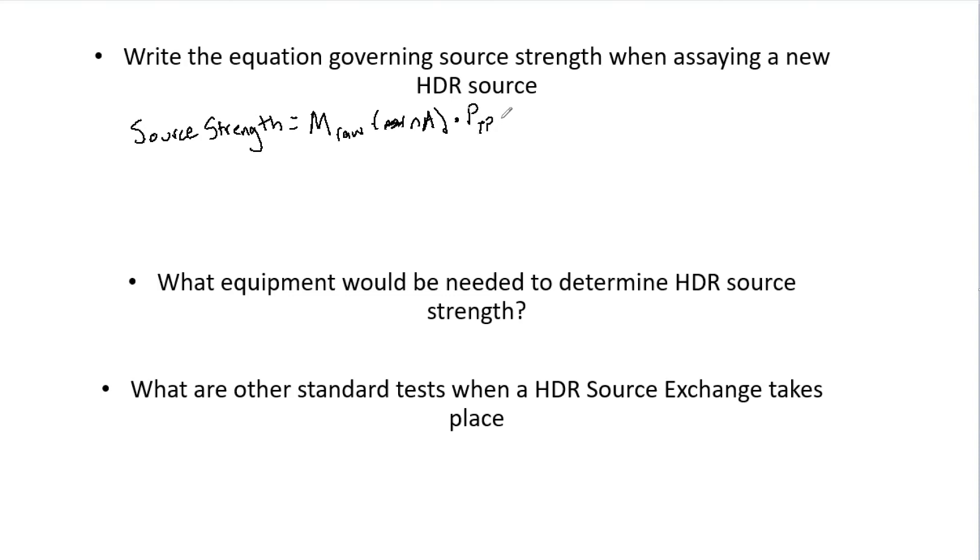So first you have that. Now you have a temperature pressure correction, just like for an ionization chamber when you do a LINAC. There is a new factor here called A-ion. This is the charge collection efficiency correction. You get this at the calibration time from the ADCL. Most of the time this is 1.0, but obviously will be determined based on your chamber.